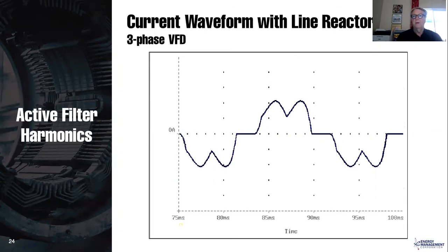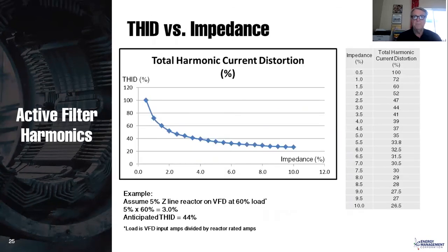So if you can't tell, I'm a big fan of reactors. Every drive can include reactors, and as I say, they're cheap. They protect against surges. It's just a really nice, easy, simple, reliable technology.